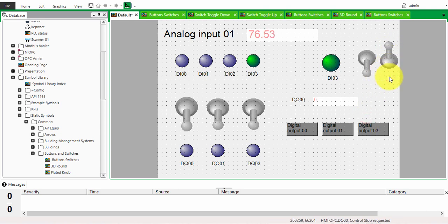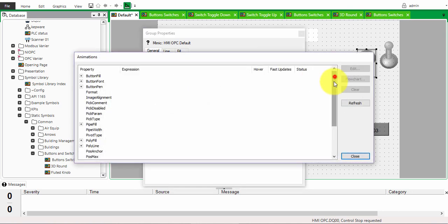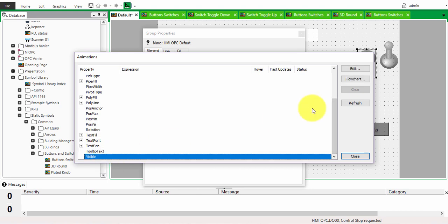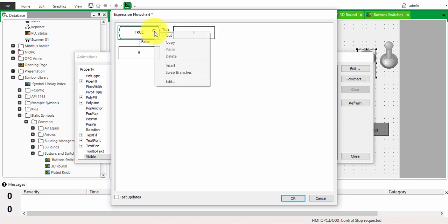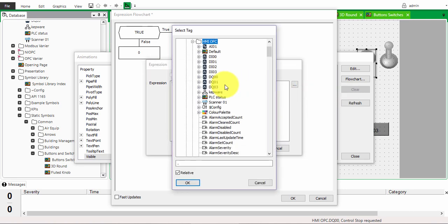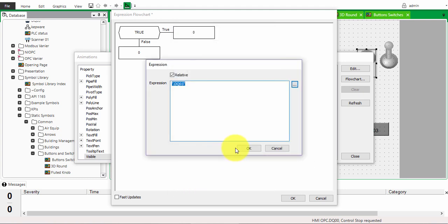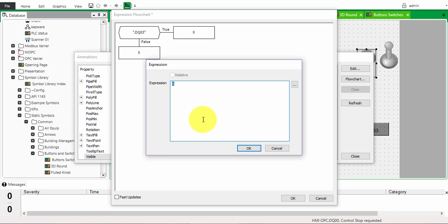Double-click on the first toggle switch image, go to animation, then go to the visibility or visible property. In the flow chart, hit insert. Click edit and from the OPC, tag it to the point you want to control — let's take DQ03 — and hit OK. When it is true, it is invisible.